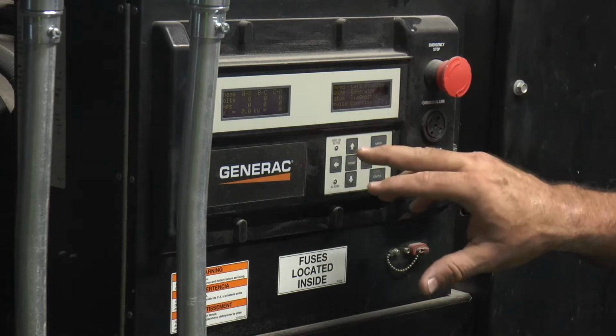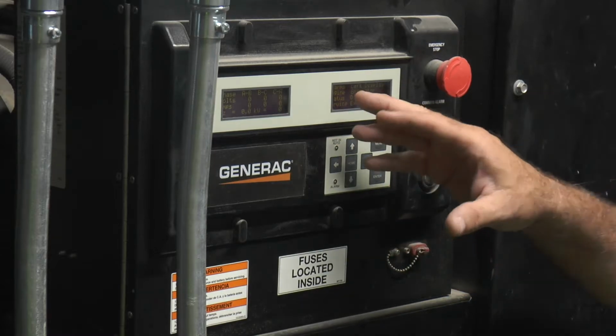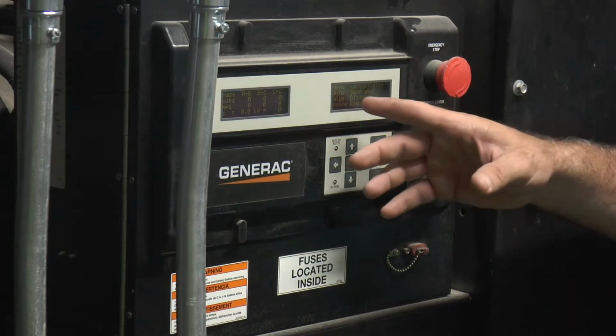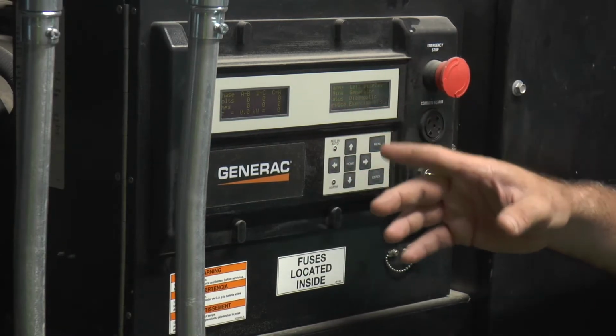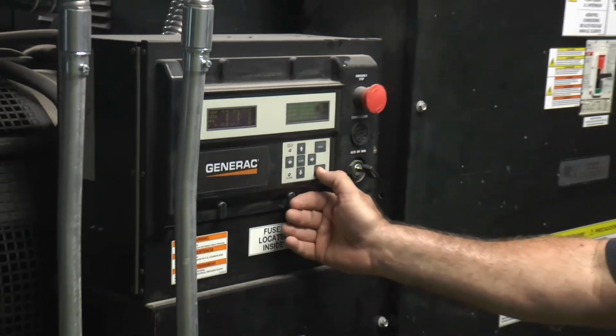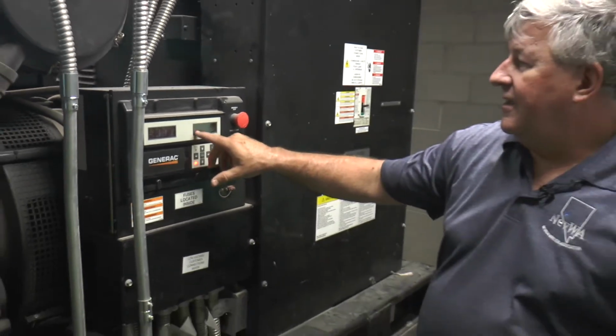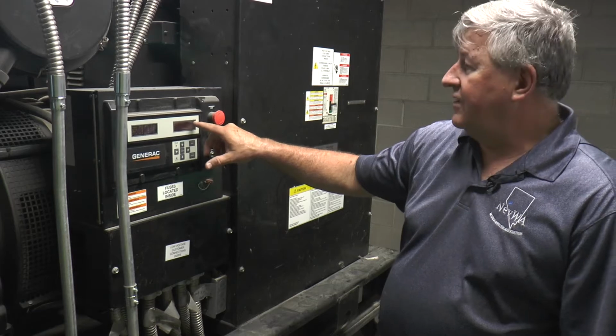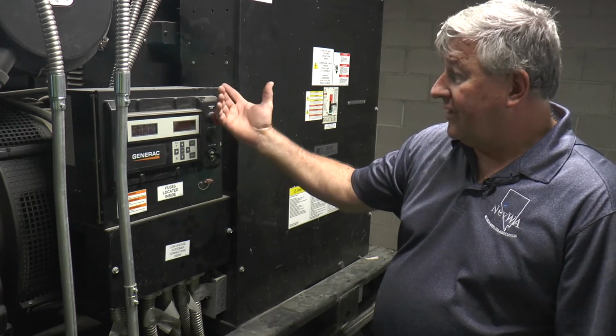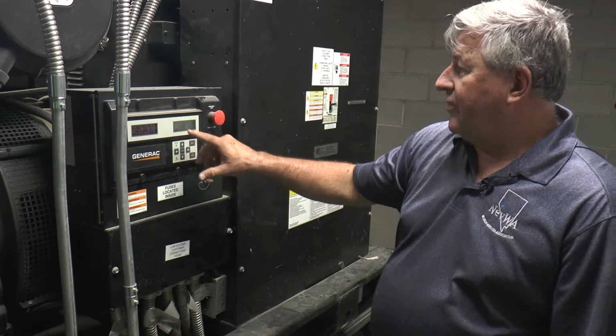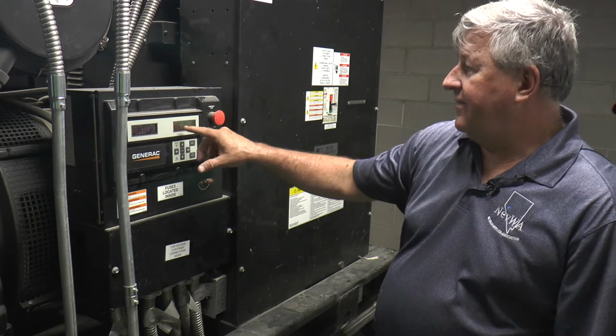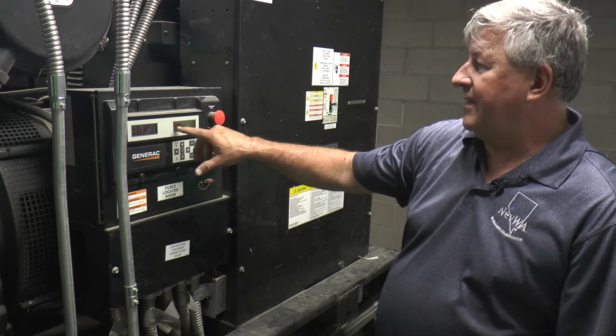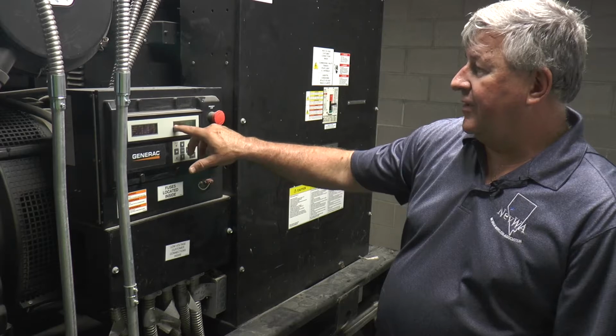It operates through a menu screen. There's a cursor that blinks that tells you where it's at. Upon pressing enter, it will give you the acknowledgement of any faults that are on the generator set. Currently, there are no faults. Home brings you back to the first screen. Menu brings you back to the menu screen.